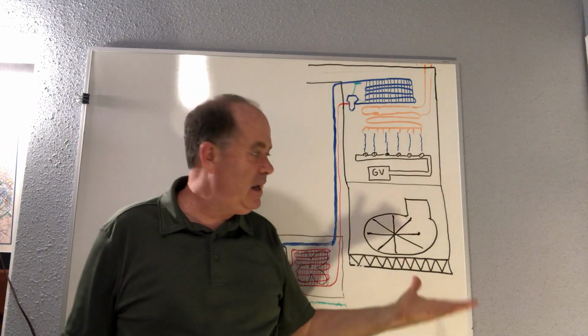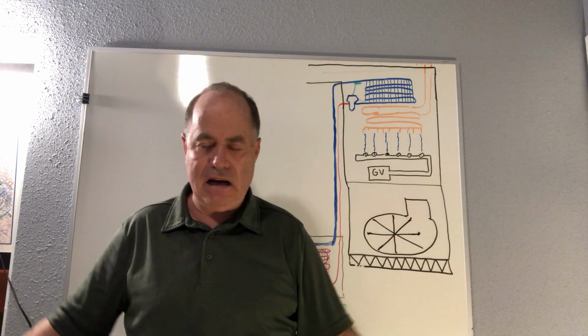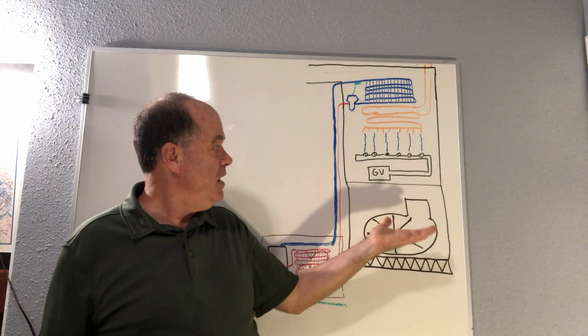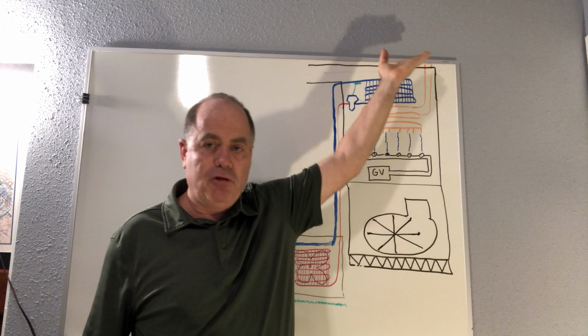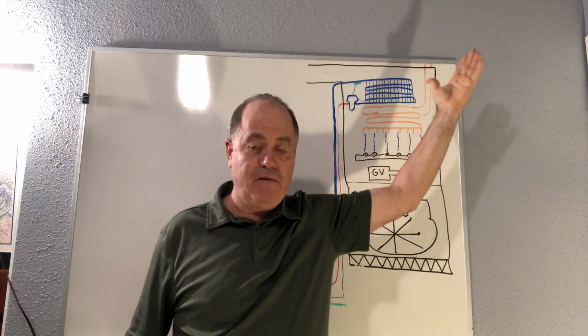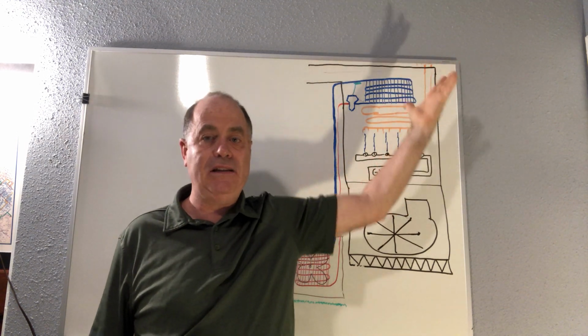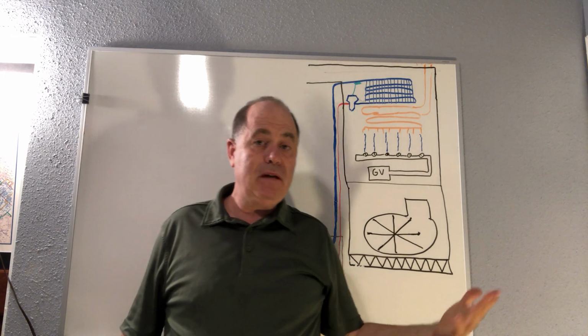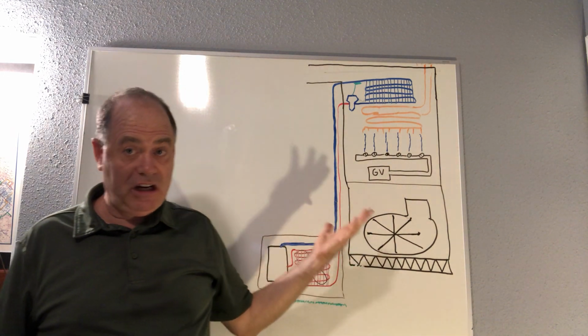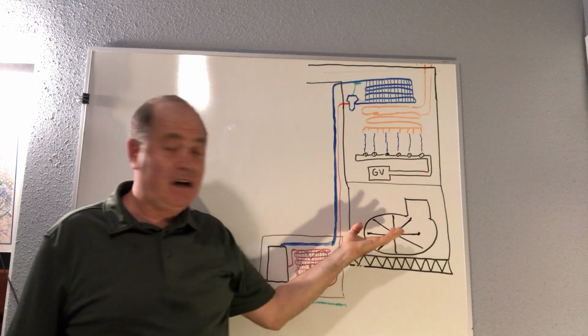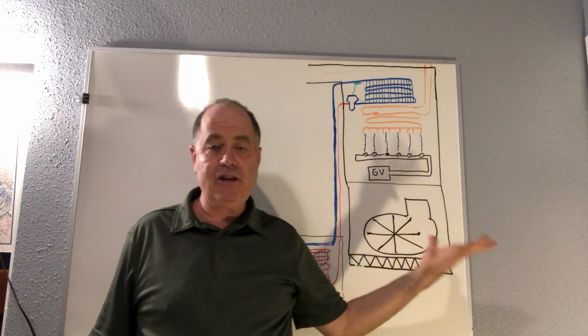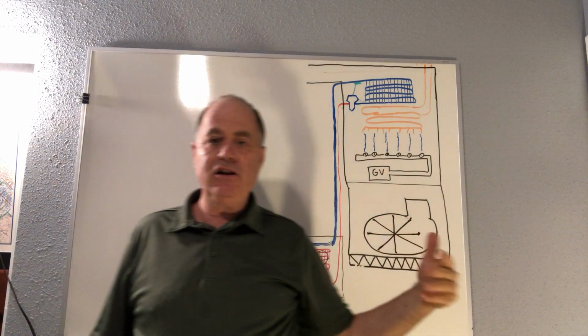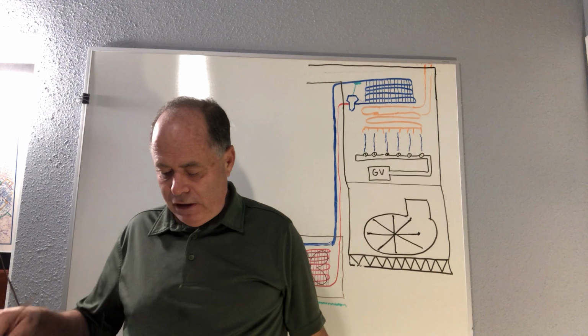But then does the fan have enough air to provide that high speed? Does it now have enough air strength to overcome the pressure drop of that evaporator coil or chilled water coil in the ductwork? And maybe you have to change the ductwork or upsize the fan motor or change the pulley ratio or whatever to get the air you need for cooling.